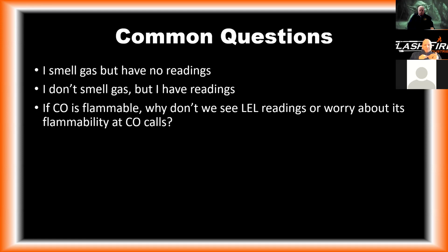Now, the exception to that is when we're talking about underground confined space areas. If we have a manhole fire, you guys saw Greenwich had one a couple weeks ago, and if you have underground utilities running and those wires start to burn under there, they create a tremendous amount of carbon monoxide, and that could potentially create a pocket of CO that has our 12.5% LEL mixture in there. And then if that hits a circuit breaker or an electrical panel, that could be the spark that ignites it underground. So if we're getting CO migration underground, although maybe in the basement you're only getting 500 parts per million of CO, you have to consider that in a very confined area somewhere else, there could potentially be an explosive level of carbon monoxide. So that's something to definitely keep in mind.